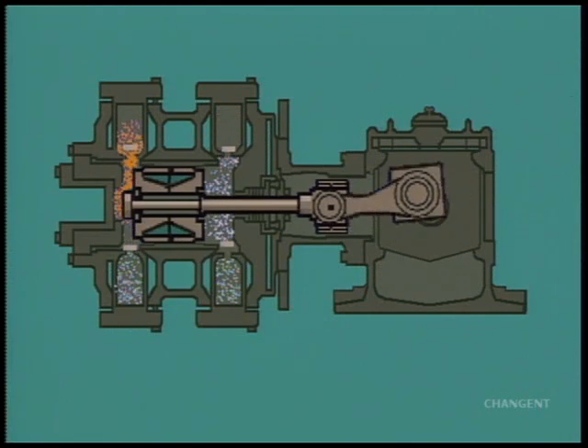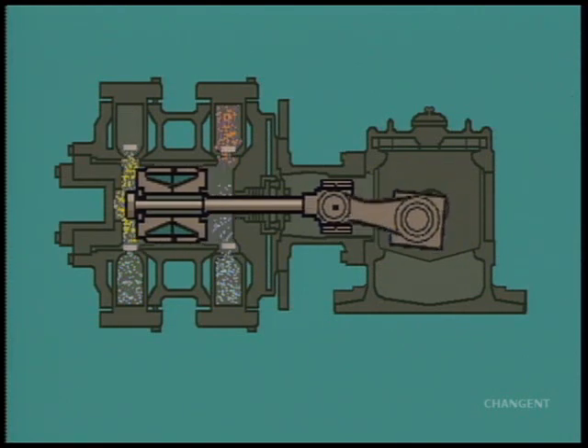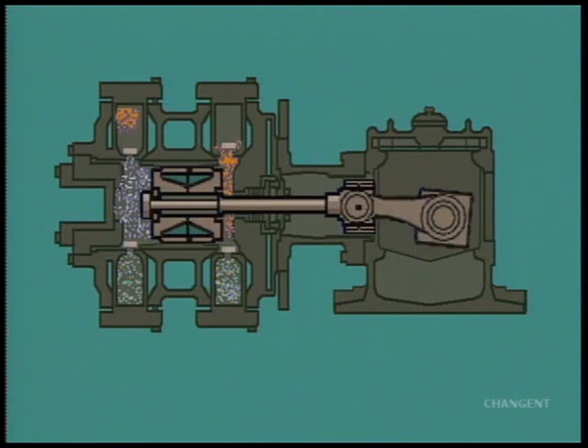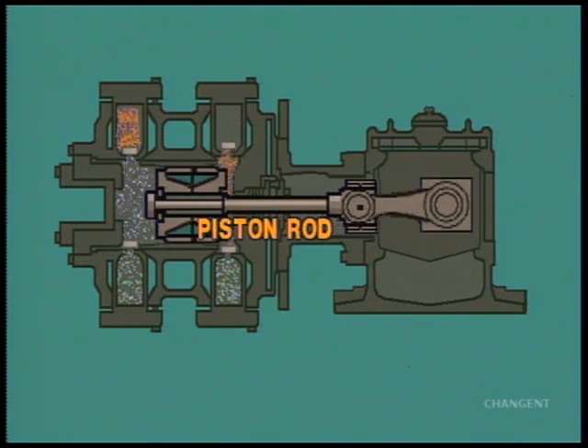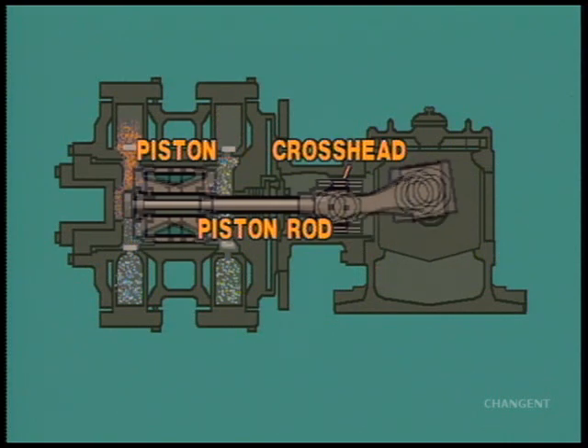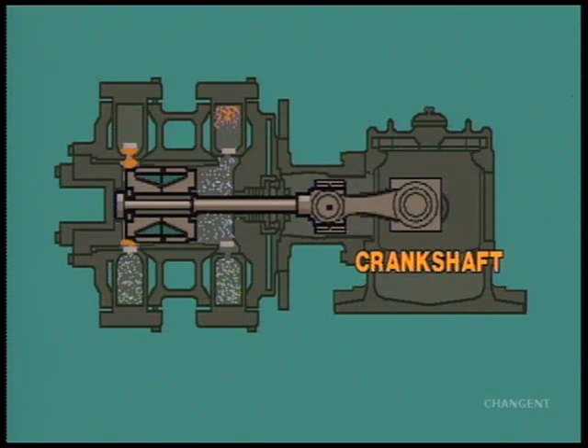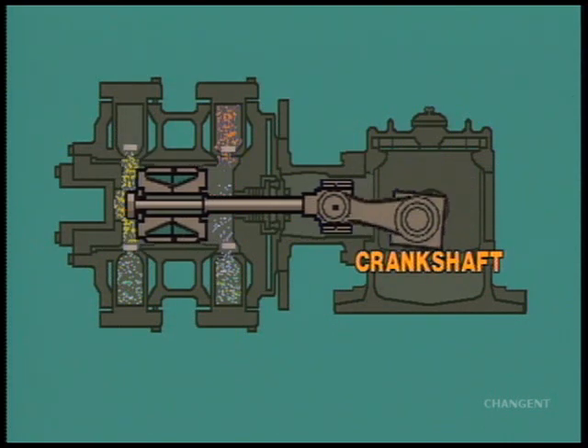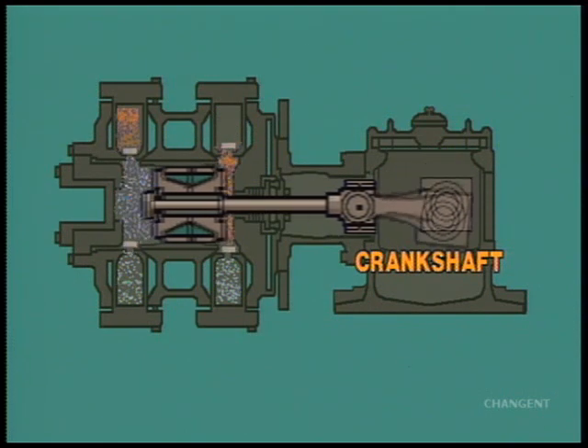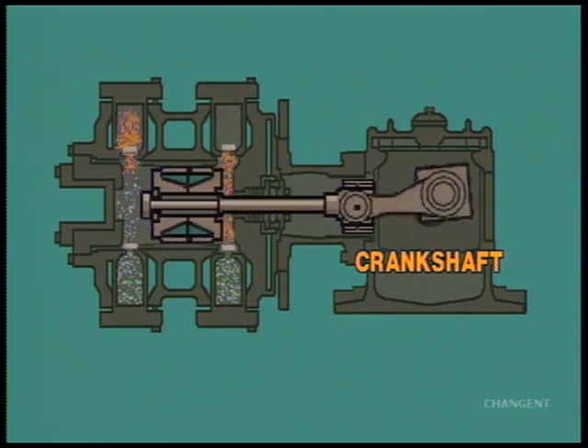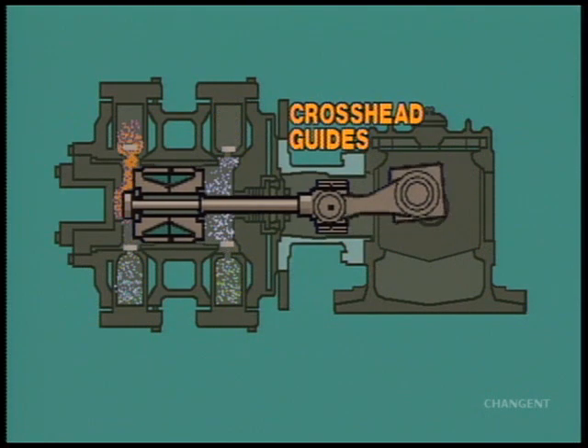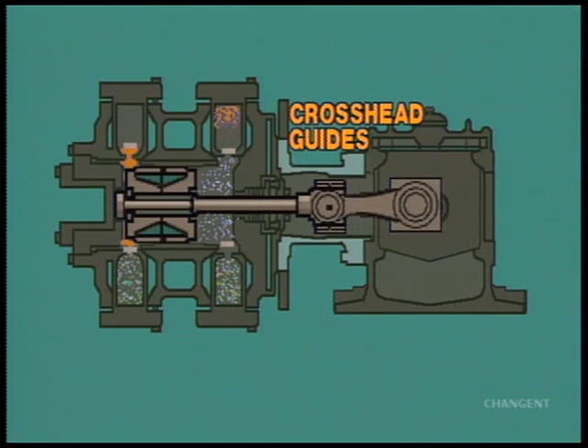Within the compressor, there are two types of rods: piston and connecting. A piston rod joins the piston to the crosshead. The crosshead converts the rotary motion of the crankshaft into the back-and-forth motion of the piston. The crosshead must be held in very close tolerance to the crosshead guides to ensure horizontal, level motion of the piston.